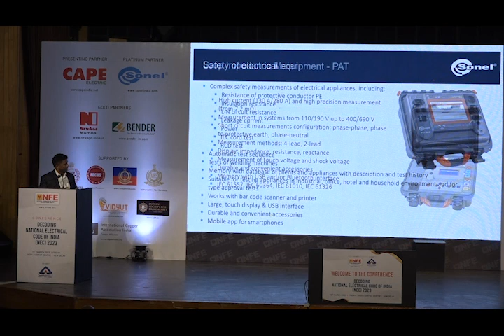According to 61557, if you make a measurement of 1 ohm, it still falls within the limit, which is 6%. But when you make a measurement of 0.13 ohm, the error could go up to 30%, even when you choose a 2% accuracy instrument. So please be a little cautious while choosing the accuracy of this equipment.